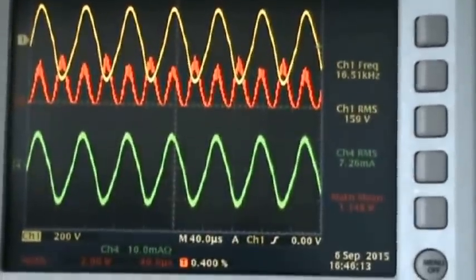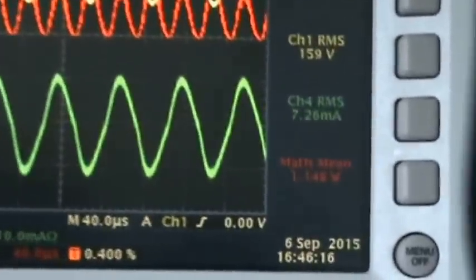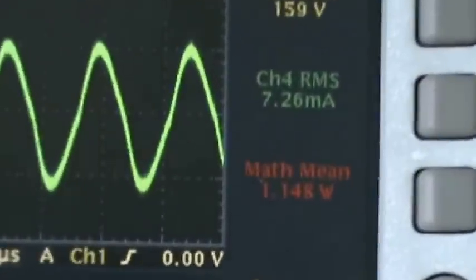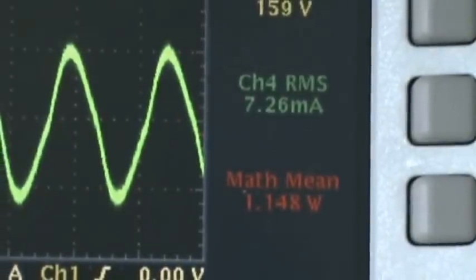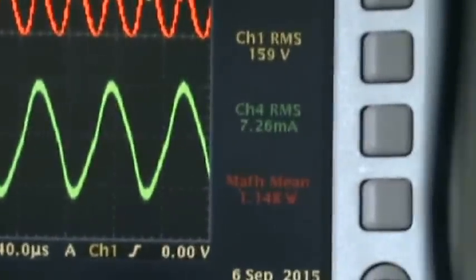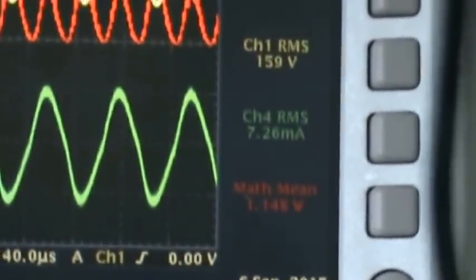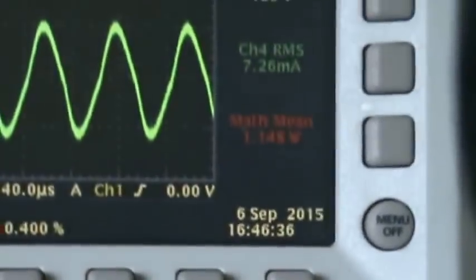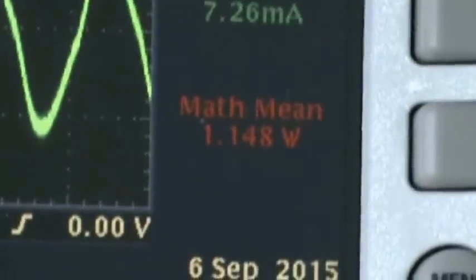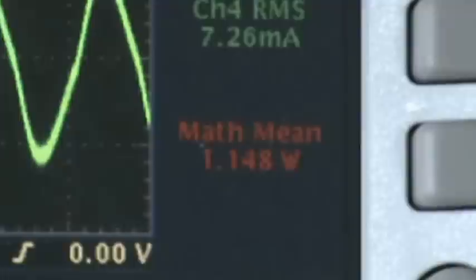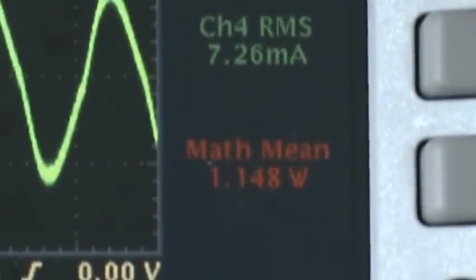And we can see that the current, the green trace, is 7.26 milliamps. We have to take this times 100 because of the setting of the current probe, so we have 726 milliamps RMS, and calculated wattage is set here at 1.14 watt, but we also have to take this times 100, so it's 114 watts going into the two bulbs and not 200 watts.